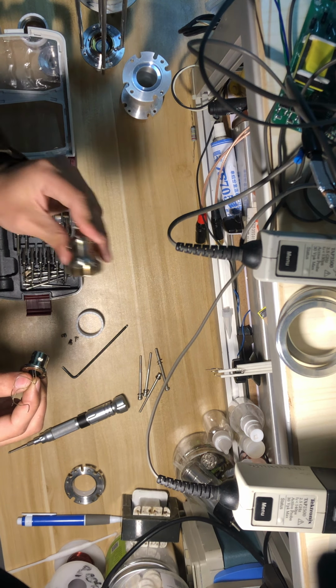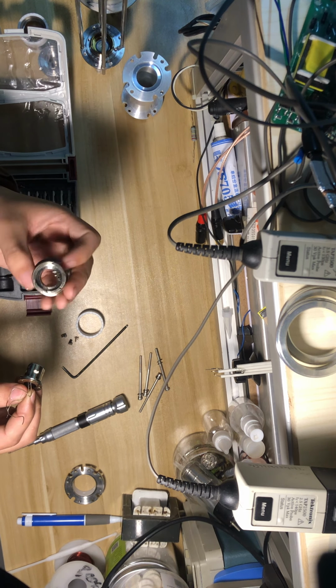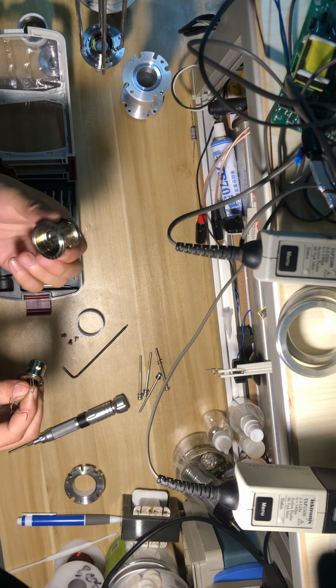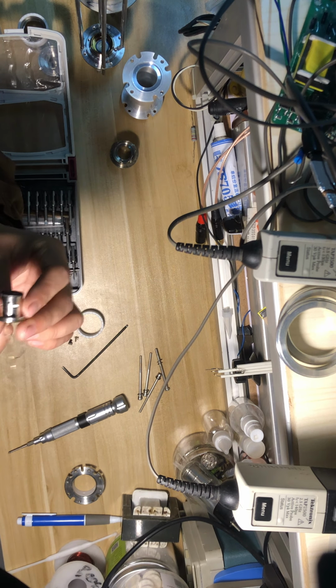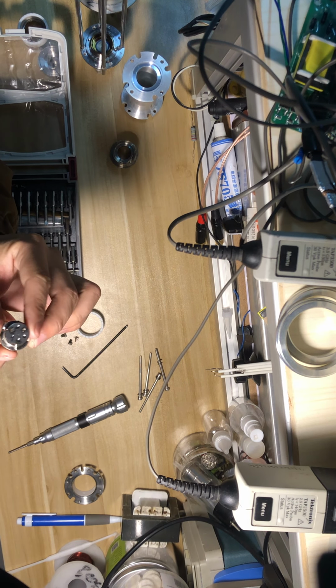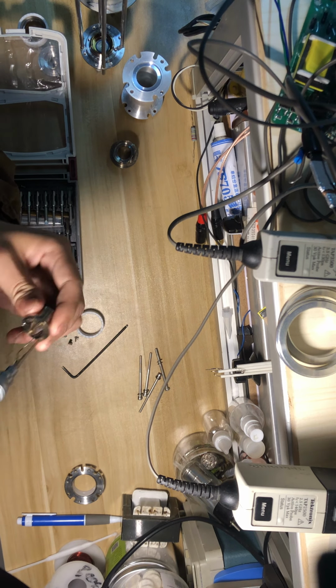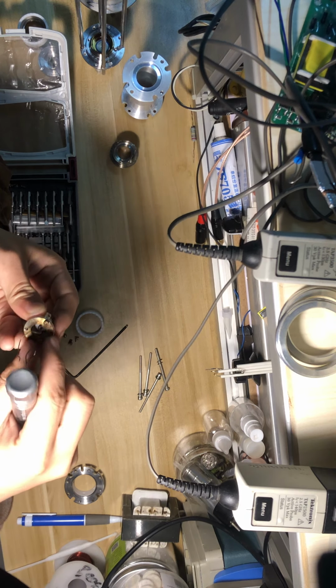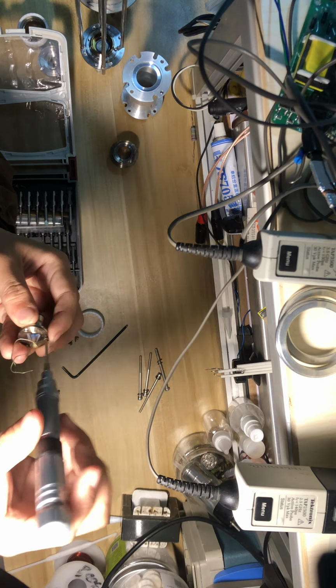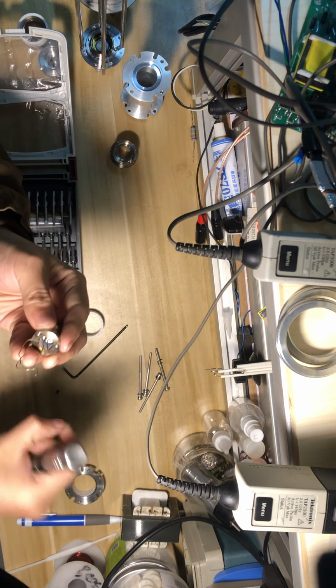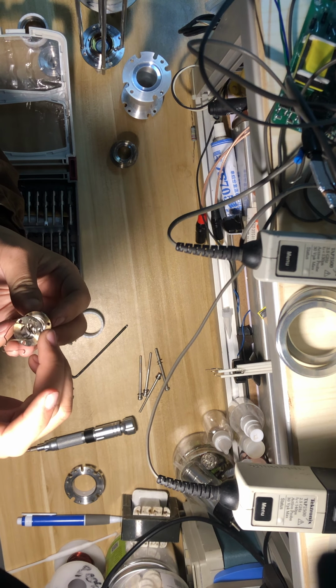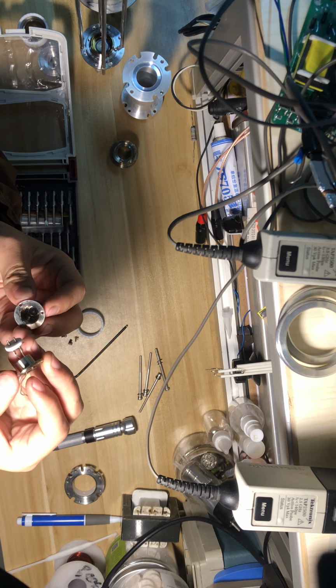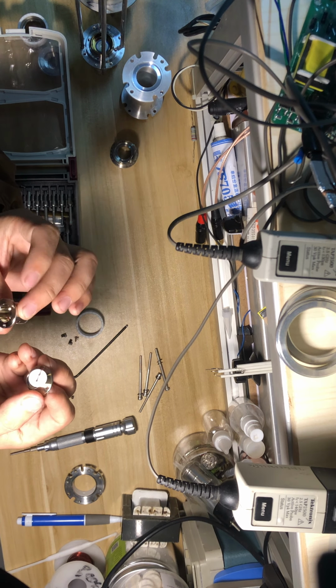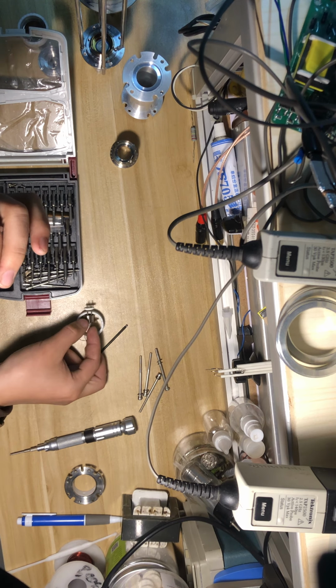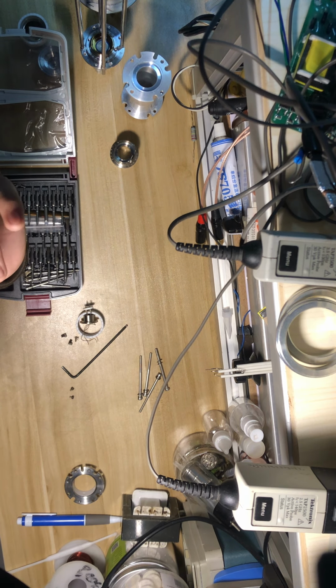So this is the Wehnelt hole, or the grid holder. There's not much inside of this. It's pretty well machined from stainless steel. Okay, this is the whole assembly of the grid, or the Wehnelt cap, and the filament. Now there are 3 screws, but there's a missing one, so I don't know what happened. Okay, we got the filament out of the Wehnelt cap. This is the Wehnelt cap. This is the Wehnelt hole, or the grid. This is the filament.